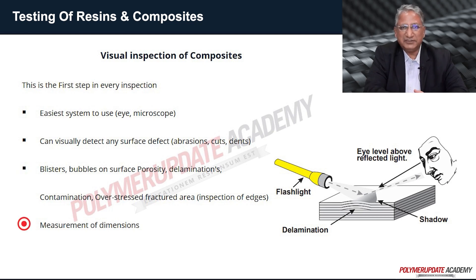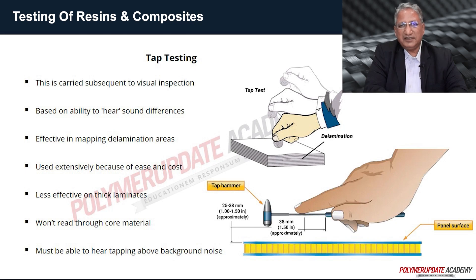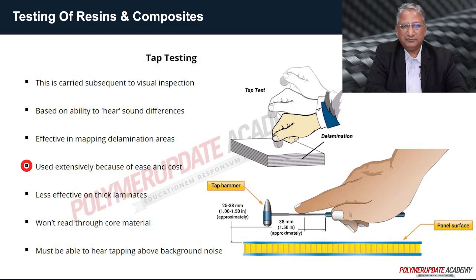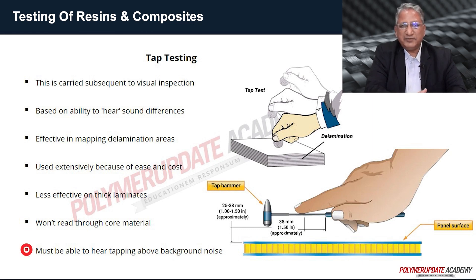After visual inspection, tap testing is carried out. It is based on the ability to hear sound differences and is effective in mapping delamination areas. It is used extensively because it is easy and cost effective. However, it is less effective on thick laminates and will not read through core material. It is important that you must be able to hear tapping above background noise.